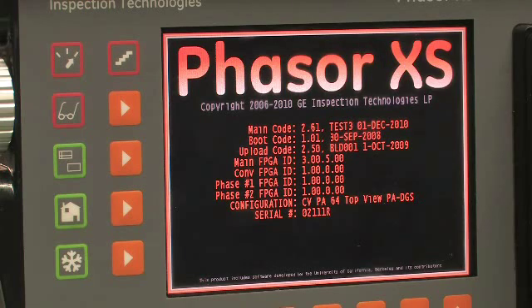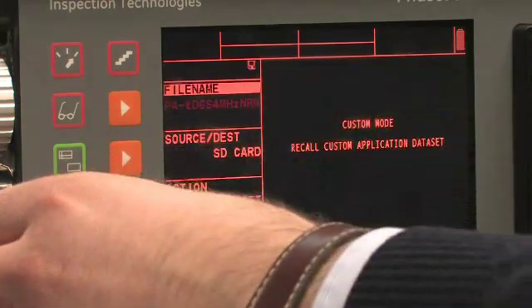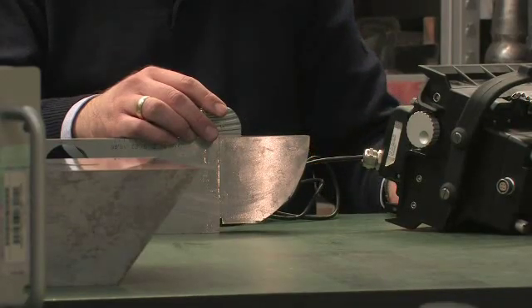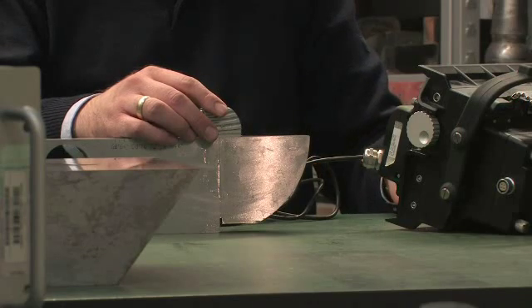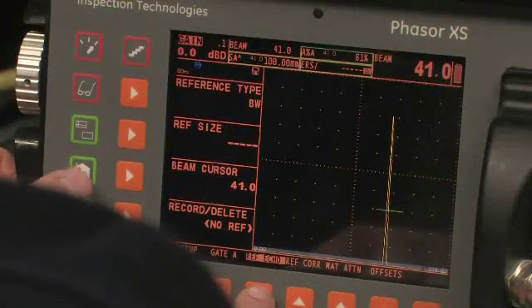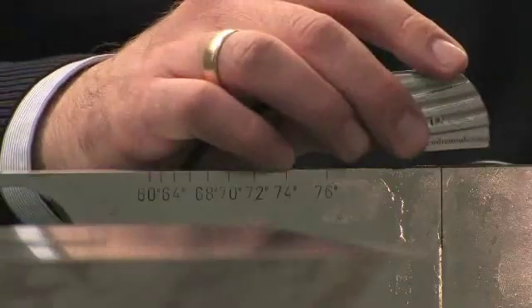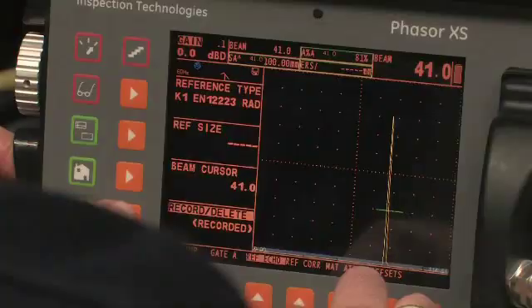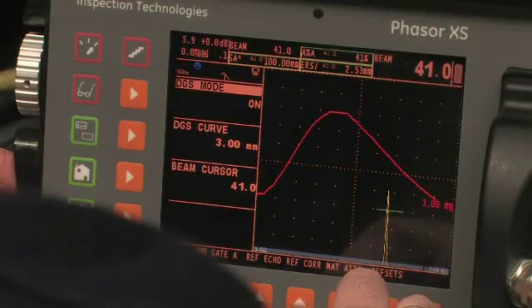After you have loaded the instrument setup available within each True DGS phased array probe, you can set up the instrument the same way you would set up a conventional flaw detector. The first step is to record the DGS reference echo. Please note that you can either record the echo on a back wall, a flat bottom hole, or on calibration block number one. All necessary correction factors come in the setup file supplied with the True DGS phased array and do not have to be entered manually. Switch the DGS mode on and choose the desired DGS curve.